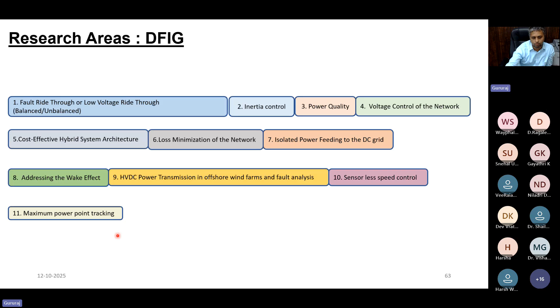So in the hardware, you have crowbar protection, where you actually short circuit the rotor during the fault and try to protect the converters. But the challenge is the machine will now behave like an induction motor. So there are two expectations from a double-fed induction machine or any inverter whose capacity, if it is more than 5 megawatt, as I remember, IEEE 1547 standards clearly indicate that the renewable power plant should get connected during the time of faults and also support the grid by injecting the reactive power.